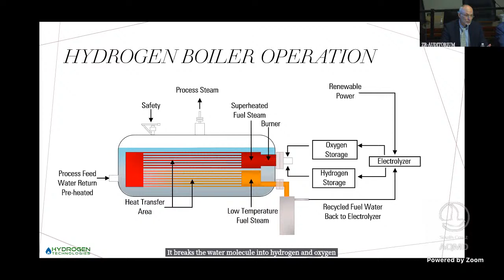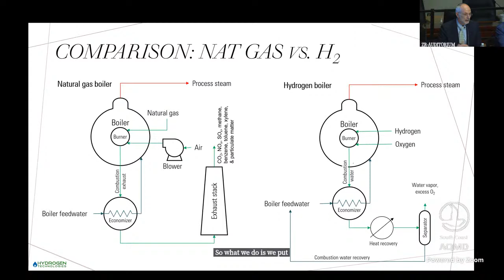So how does it compare to natural gas? On one side, we've got the natural gas boiler, and it's got an air blower at the front because we're trying to oxidize the methane gas we're using for fuel. We want the 20% oxygen that's in the atmosphere, so we force it into the burner area. 78% of the air we push in is nitrogen, 20% is oxygen, and that's what we want. We put 5 times the volume of air into this burner to get the oxidation, which creates the heat and the steam. On the backside, we've got to blow that air out an exhaust stack, and out that stack comes CO2, NOx, methane, benzene - that's the witch's brew of things created inside the thermal chamber of that boiler.